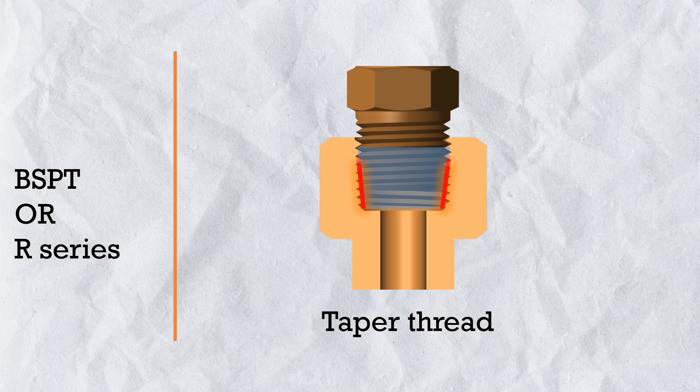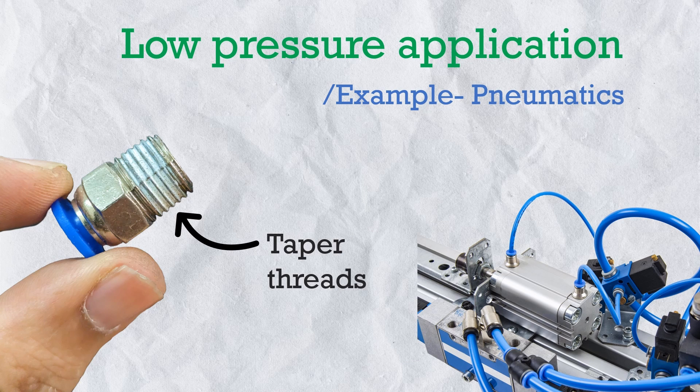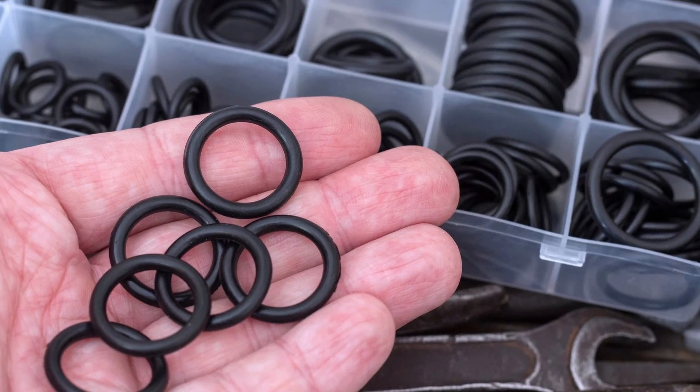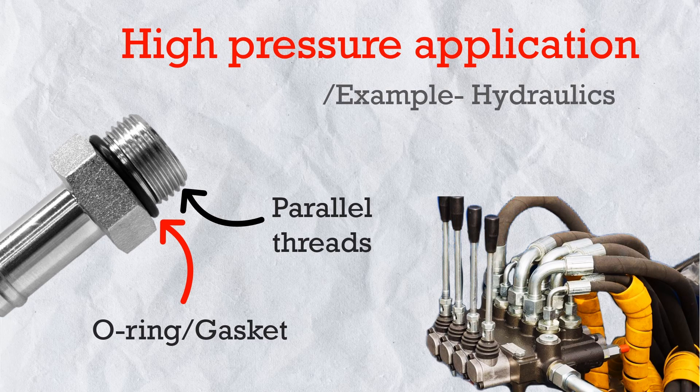If you have worked in hydraulics, you may wonder why we rarely see tapered threads in hydraulic fittings. Since R thread is a sealed tapered thread, why don't we use it? Why do we use BSPP parallel thread with O-ring or gasket instead? Here is the reason: taper thread seals the connection through thread interlocking and the sealing tape over the thread. Because of that, for low-pressure applications like pneumatics, taper threads are better since we don't need extra sealing elements like O-rings or gaskets. But in high-pressure applications, we cannot trust the sealing capacity of taper thread interlocking alone, so we always prefer parallel thread with proper sealing elements like an O-ring or gasket.